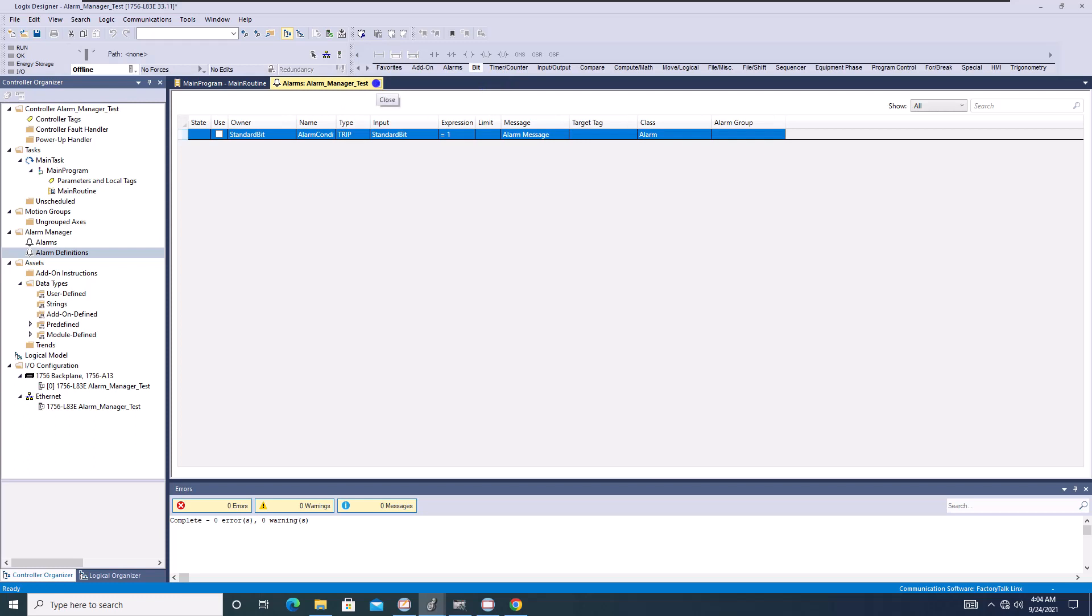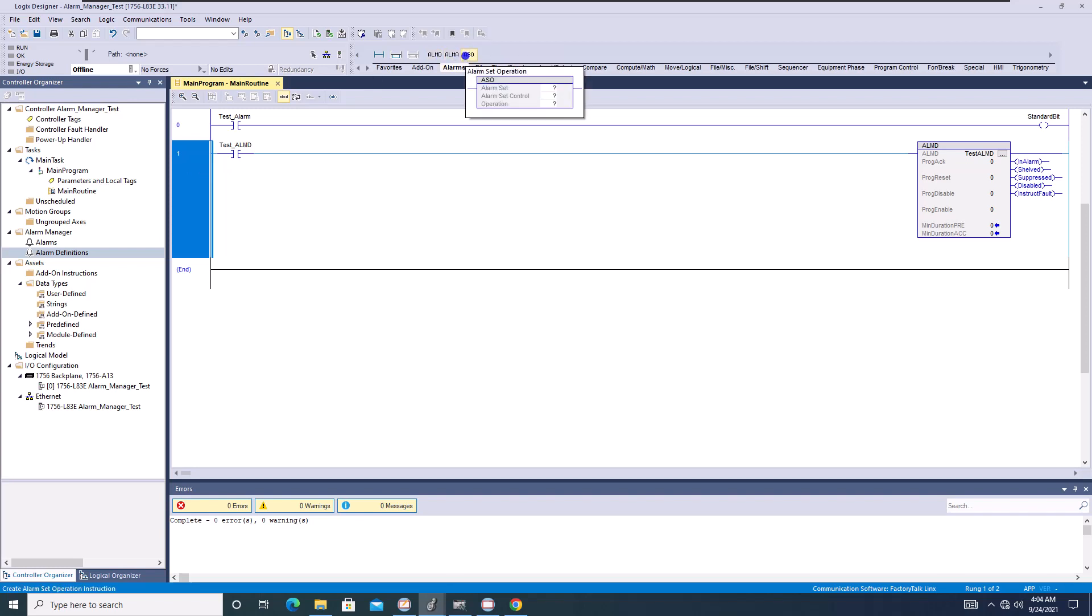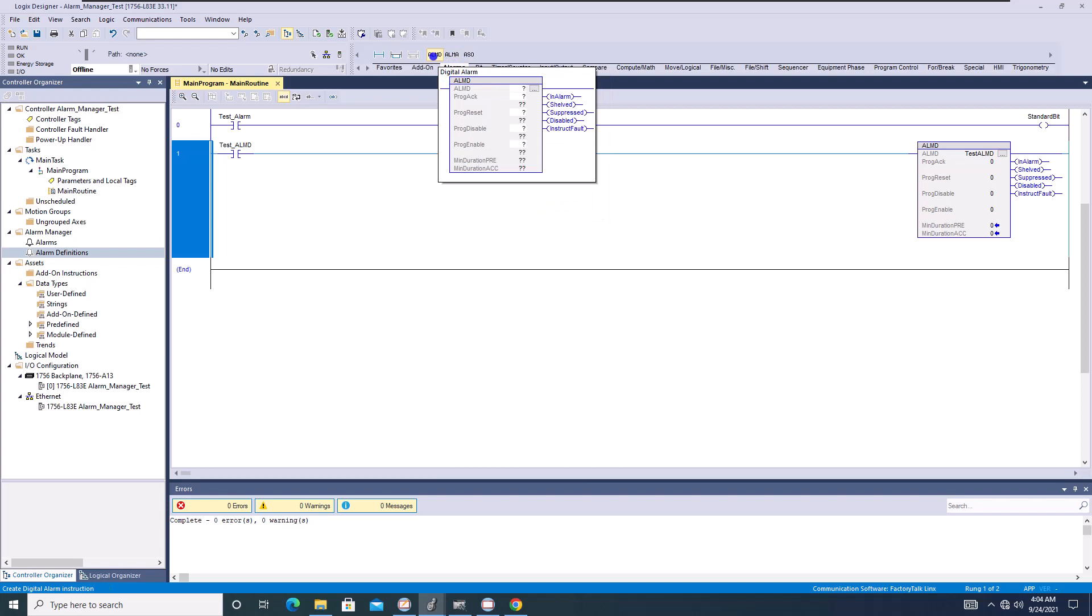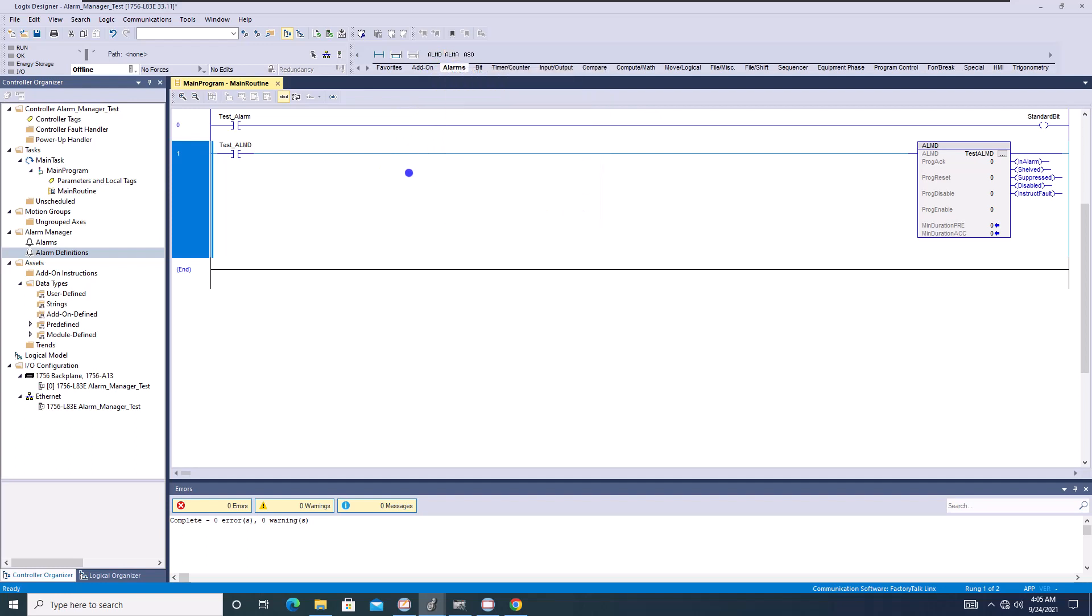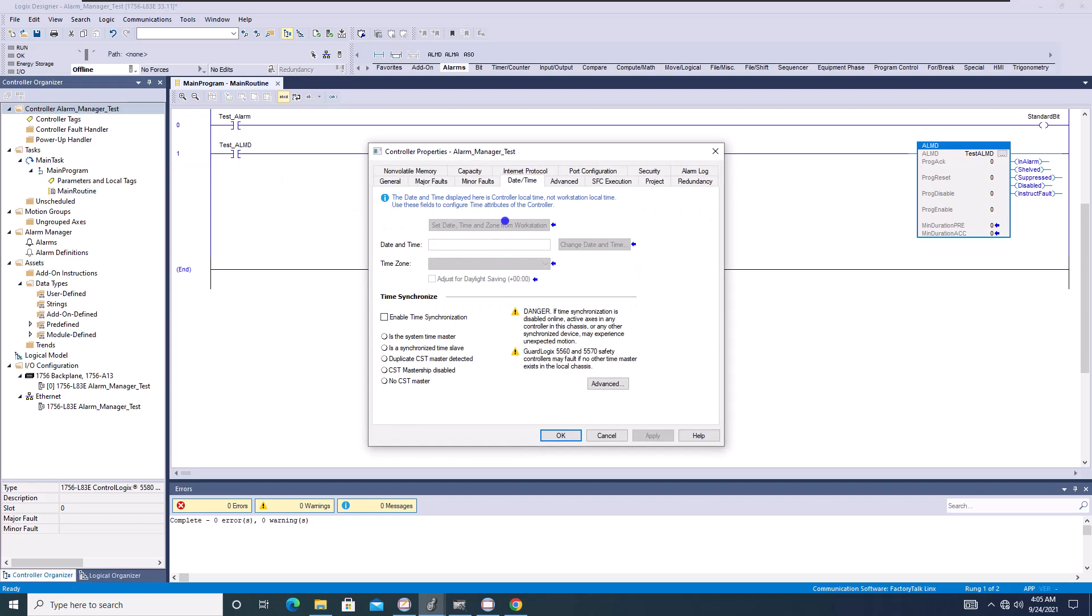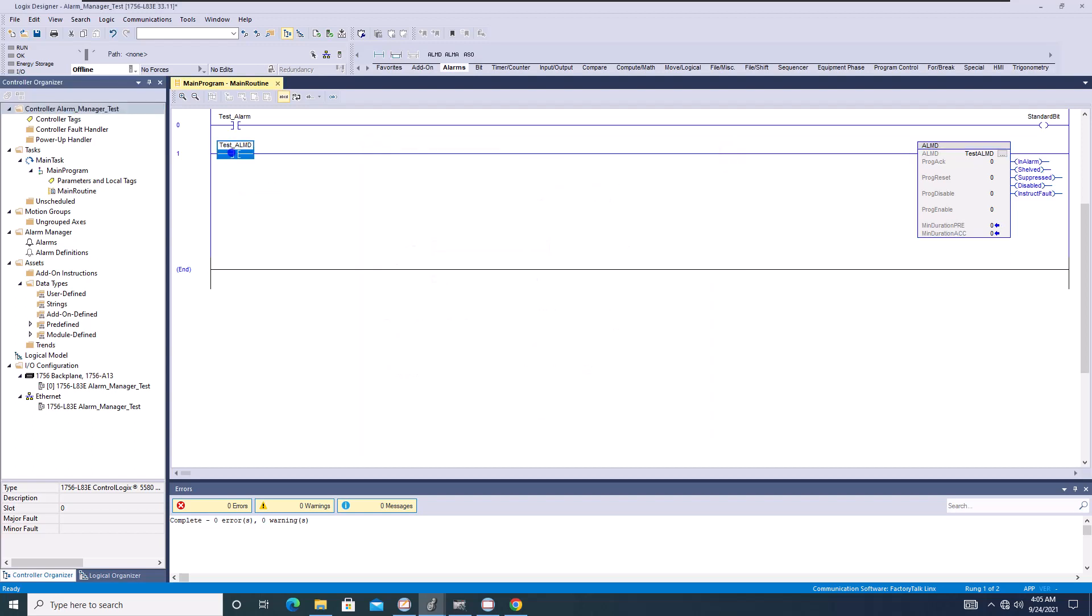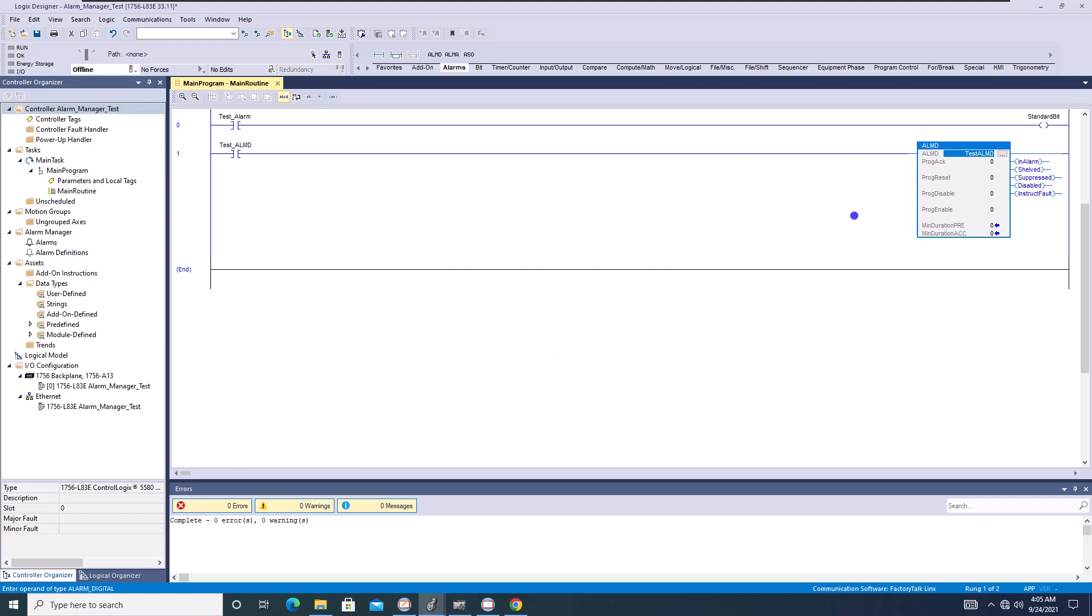Well, but the key components, I would say when you're looking, if you're trying to decide, should I use alarm manager or should I use an ALMD? Now keep in mind, ALMDs and ALMAs, which are up here, right? Have been around for quite some time. The ALM, ALMD and the ALMA, which ALMD is the digital, ALMA is the analog version. They've been around for quite some time and are tried and true and are timestamped to the actual controller level. So the timing of the controller, so if you were to go into the controller properties and you were looking at date and time, it would match the date and time of when it, that's when the timestamp would happen. When this bit right here was triggered and it would activate as soon as it came into an alarm, it would put that timestamp in there. So that would be, there's no delay in that whatsoever.